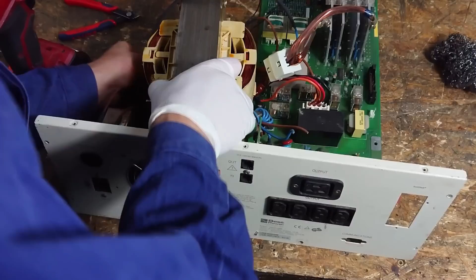In some uninterruptible power supplies, a mains transformer is part of the output stage of the inverter, but then the output winding is also tapped to act as a step-up transformer when the mains voltage is too low, like in a brownout scenario. In this case, however, the transformerless inverter and the autotransformer act completely independently, so we can just remove it. We can also remove the other external boards that connect to the main board.